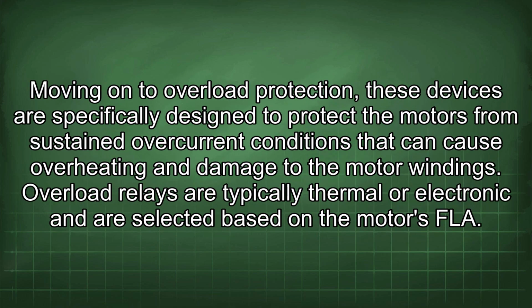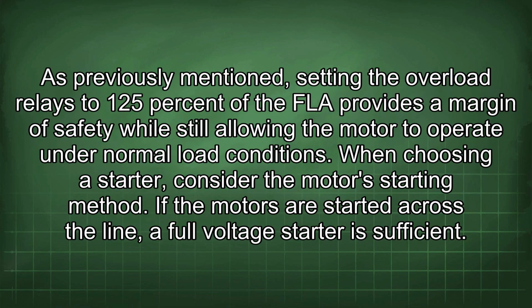Moving on to overload protection, these devices are specifically designed to protect the motors from sustained overcurrent conditions that can cause overheating and damage to the motor windings. Overload relays are typically thermal or electronic and are selected based on the motor's FLA. As previously mentioned, setting the overload relays to 125% of the FLA provides a margin of safety while still allowing the motor to operate under normal load conditions.